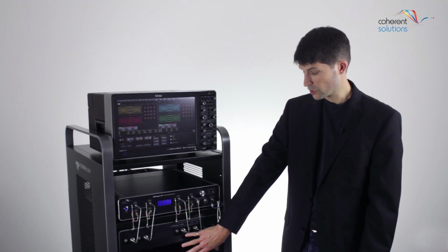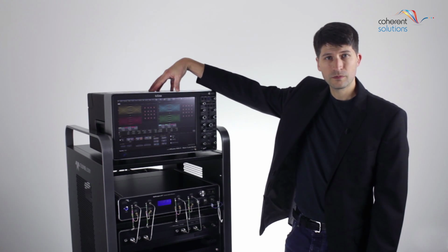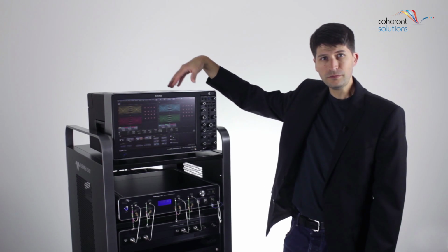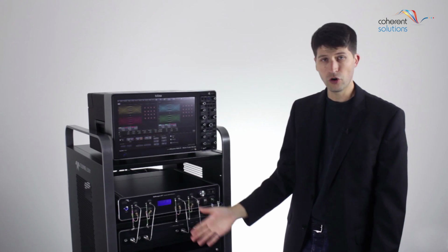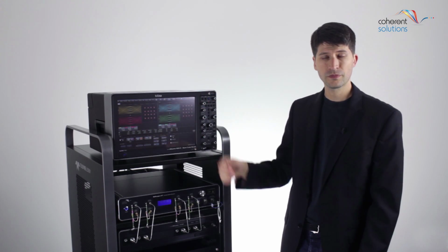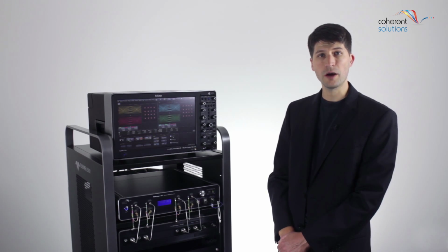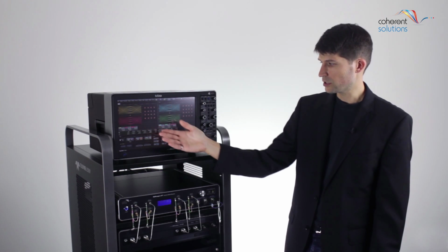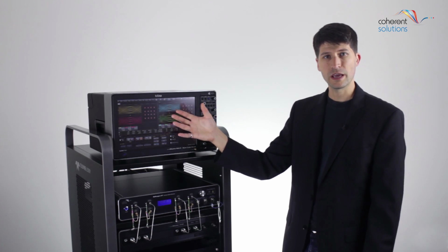Those digital signals are passed from the acquisition unit to the MCM. The MCM is a powerful processor. It contains the MAUI application which controls the entire OMA system. The MAUI software has an analysis package called the Optical Link. So all of the DSP, visualizations, and performance metrics are shown here in the MCM.